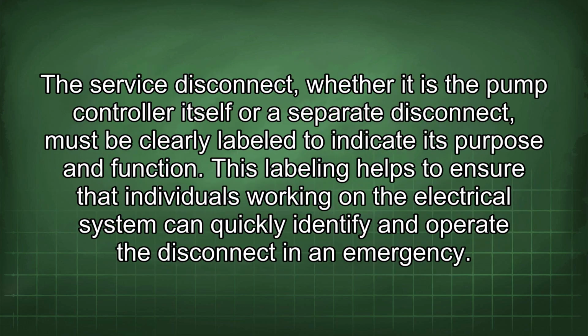The service disconnect, whether it is the pump controller itself or a separate disconnect, must be clearly labeled to indicate its purpose and function. This labeling helps to ensure that individuals working on the electrical system can quickly identify and operate the disconnect in an emergency.